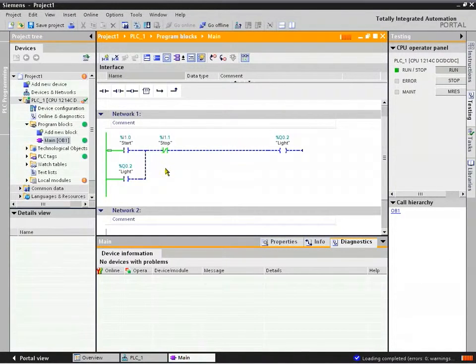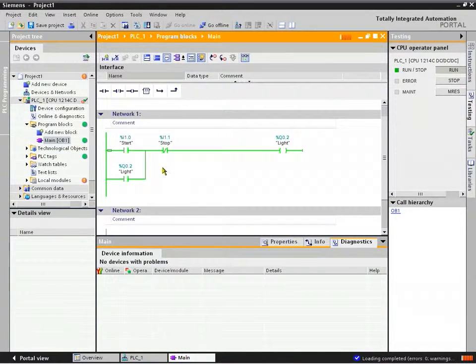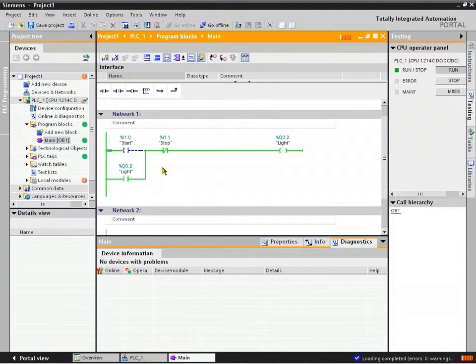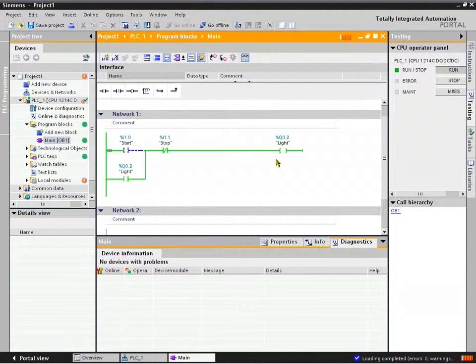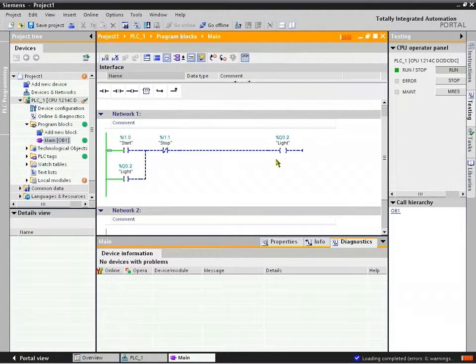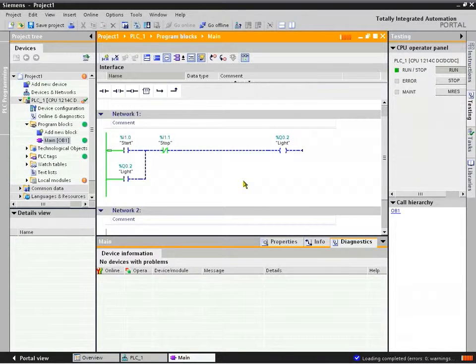When I turn on my start switch, it seals in that circuit. And I can remove my start switch as if it was a push button. It still has my output light active. And then I can break the connection with the normally closed stop button or push button. And then my circuit is complete, fully tested, and available for running.